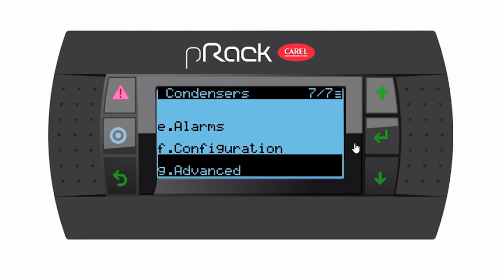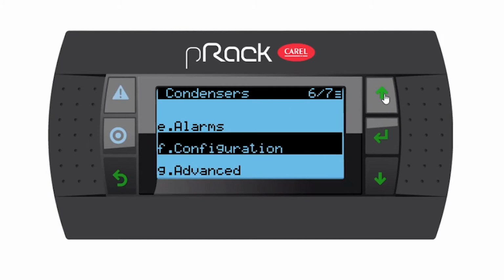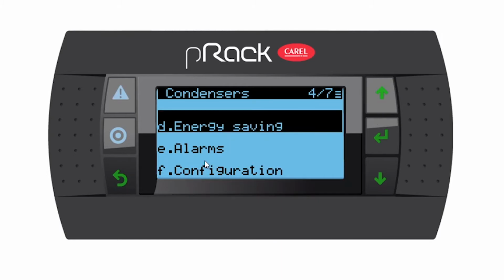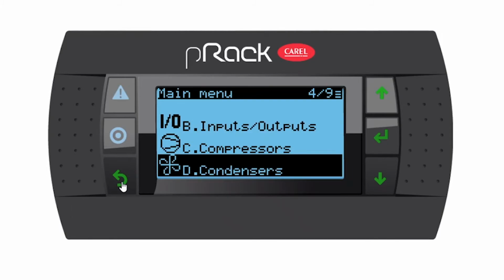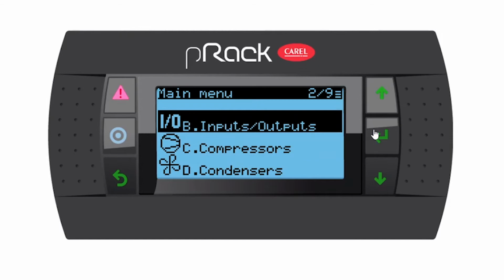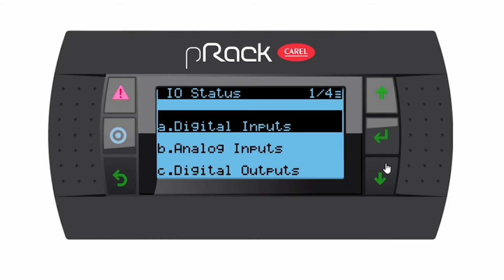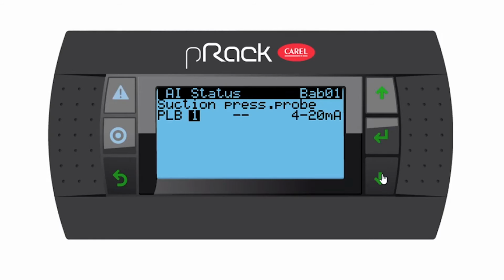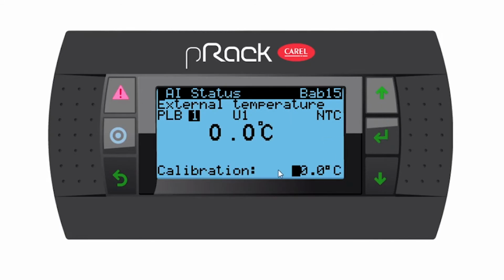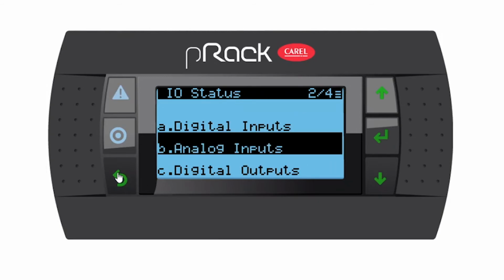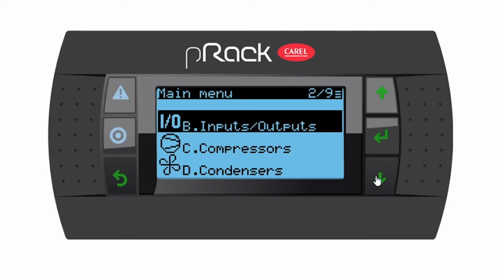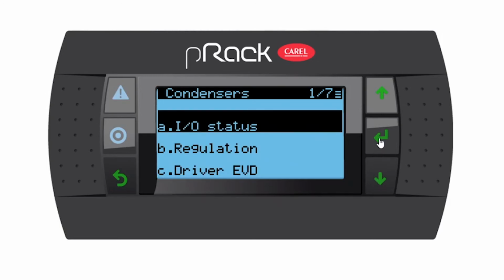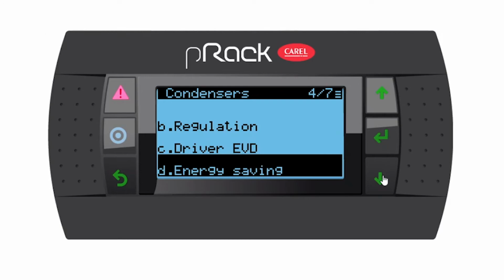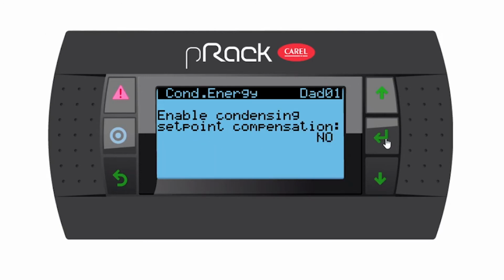So let's escape. And this is now the bonus where I'm going to show you how to set up floating condensing. But first we need to escape from this menu. Go to inputs and outputs, status, analog inputs, and we need to go and assign an external temperature. So I'm just going to assign one randomly. Then escape from this menu. Go back to the condensers, enter, and then go down to energy saving, energy saving, and enter.